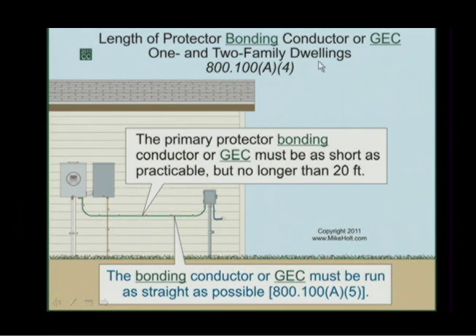The rule is, in one or two family dwellings, this bonding conductor to the inter-system bonding terminal can't be longer than 20 feet. Why limit the length? Because you get the telephone grounded at one location at the utility, the cable grounded in one location, the building grounded in one location. A lightning event creates a voltage gradient resulting in a difference of potential. We want to bring them all to the same potential by bonding them together. But if you run a conductor longer and longer between the two systems, even though you're trying to bring them to the same potential, it will never get it to zero.